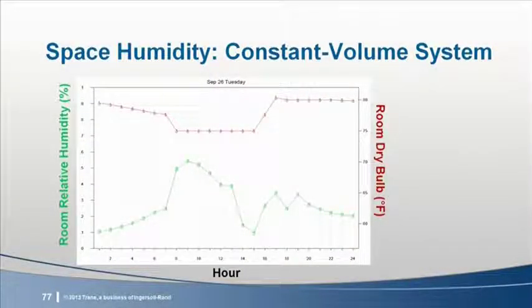The Graph Profiles and Energy program, sometimes called the Visualizer, is another tool that can be used. It can be configured to show many different variables from the simulation, both in a tabular and graphical format. In this custom configuration, I've plotted the maximum hourly relative humidity for a specific day when the school is occupied. The horizontal axis shows the hours of the day. The vertical axis on the left shows the relative humidity expressed as a decimal, and the vertical axis on the right shows dry bulb temperature in Fahrenheit.